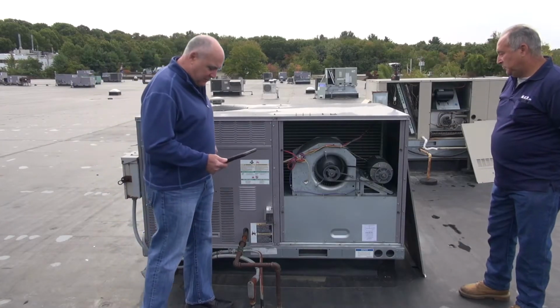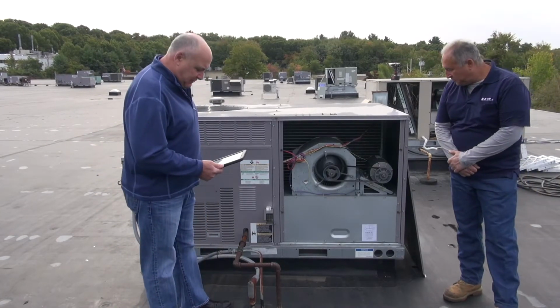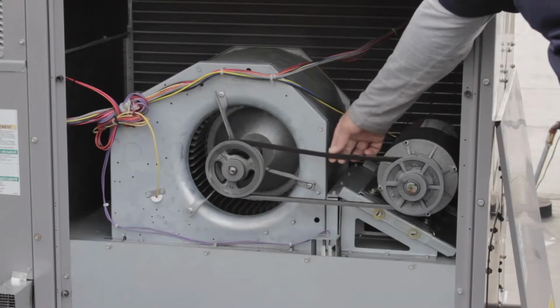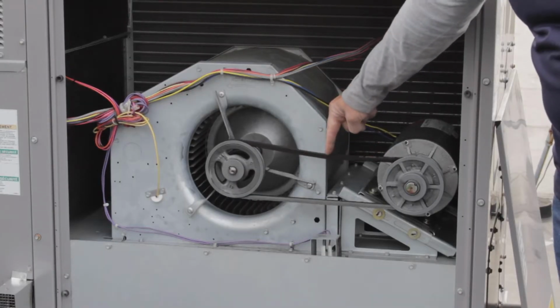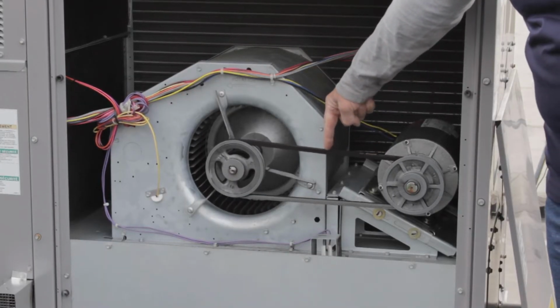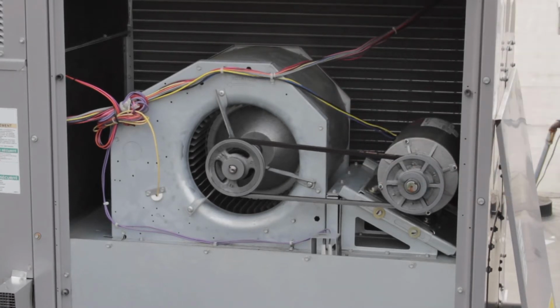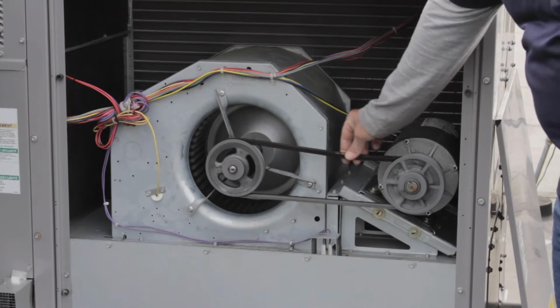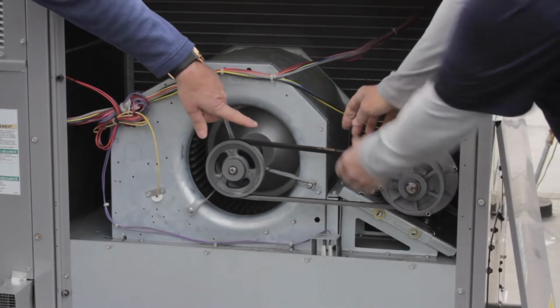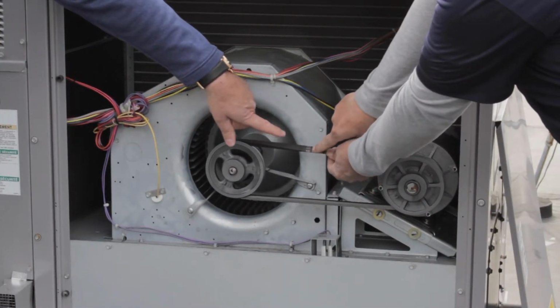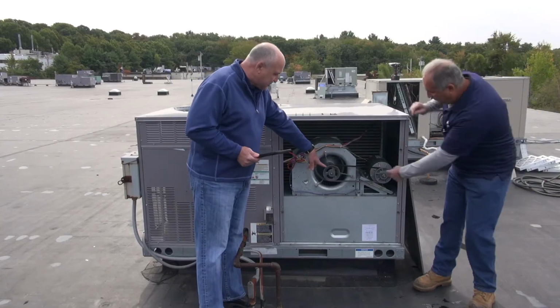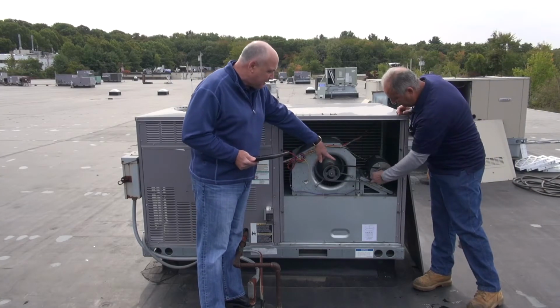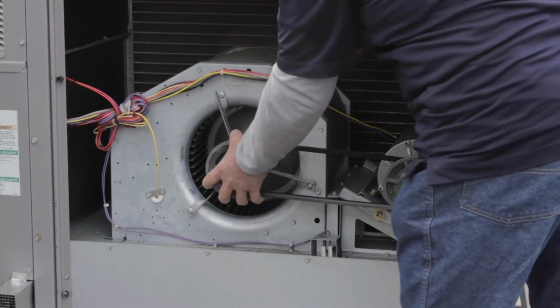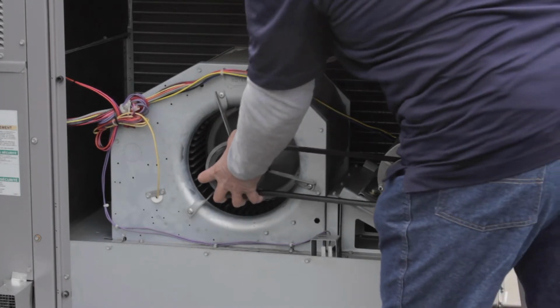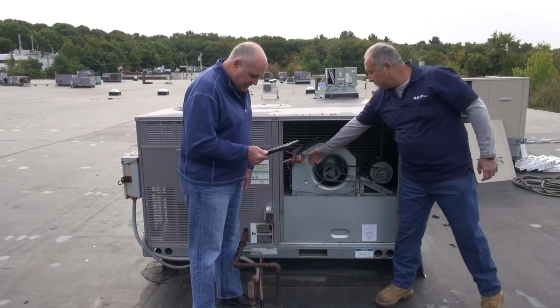The first section we look at is the blower section. We check the belt tension to make sure it's tight. We also record the belt number and the number of belts in case they need to be replaced, and we check to make sure that the belt isn't worn or cracked. We check the motor sheaves to make sure they aren't grooved, and we inspect the bearings on the blower wheel to ensure there isn't any movement, and we check the wiring.